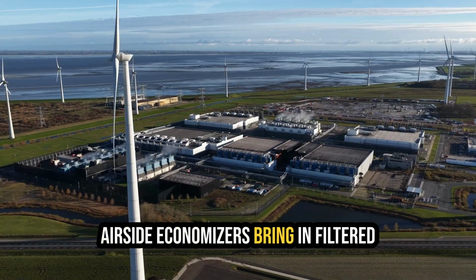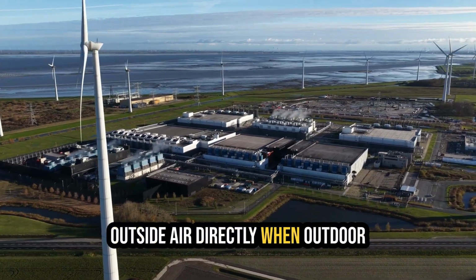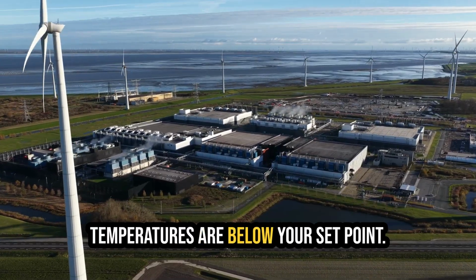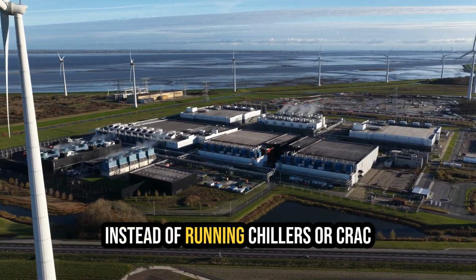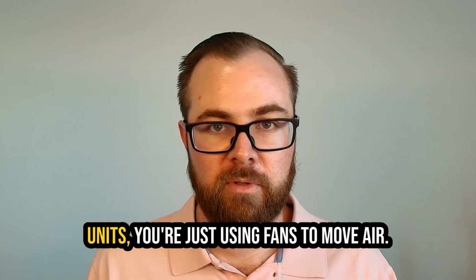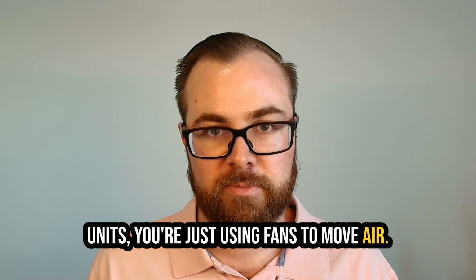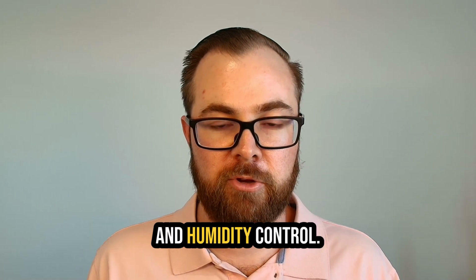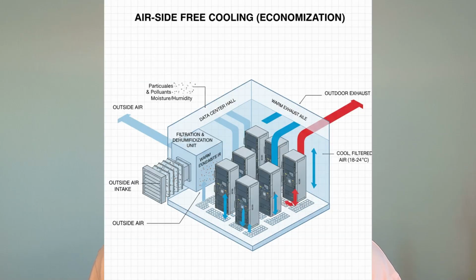Airside economizers bring in filtered outside air directly when outdoor temperatures are below your set point. Instead of running chillers or CRAC units, you're just using fans to move air. The challenge is filtration and humidity control. Outside air carries particulates, pollutants, and moisture that can damage equipment. You need robust filtration systems and sometimes supplemental dehumidification.